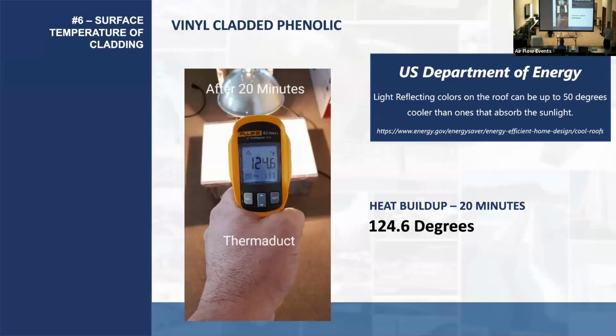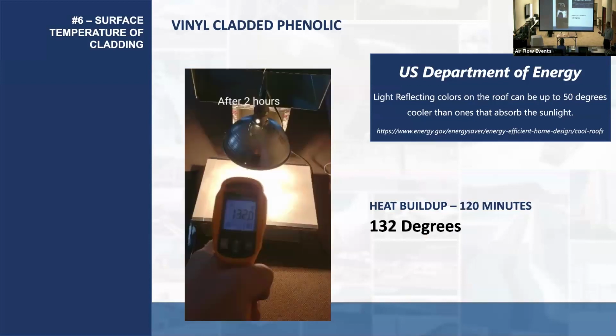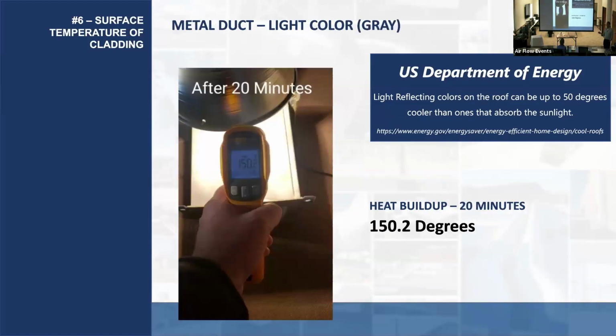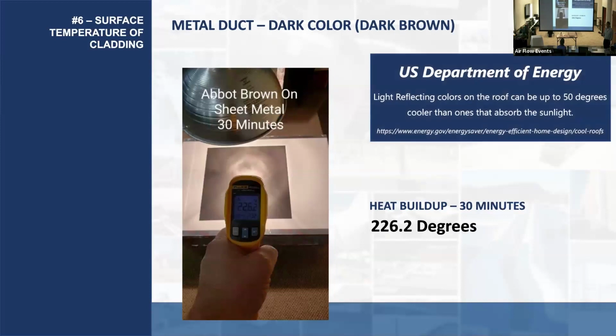This is the last thing, that white finish keeps the surface temperature of the ductwork down in summertime. Yeah, maybe there's some benefit to having a darker finish in the winter and you're picking up a little bit of solar gain. But in the summertime, even the silver stuff picks up a lot of temperature. So what color is this? The Thermaduct. This is just a test, a light test, right? And you can raise the temperature of the Thermaduct up to about 125. This is the vinyl cladded stuff, so silver picks up another 8 degrees. Metal duct, if it's internally insulated, goes up to 150 degrees. And then there's some ductwork, Abbot Brown, it's all dark brown.